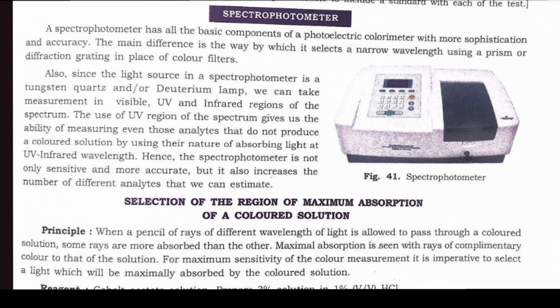The use of the UV region of the spectrum gives us the ability to measure even those analytes that do not produce a colored solution, by using their nature of absorbing light at UV or infrared wavelengths. Hence, the spectrophotometer is not only sensitive and more accurate, but it also increases the number of different analytes that we can estimate.